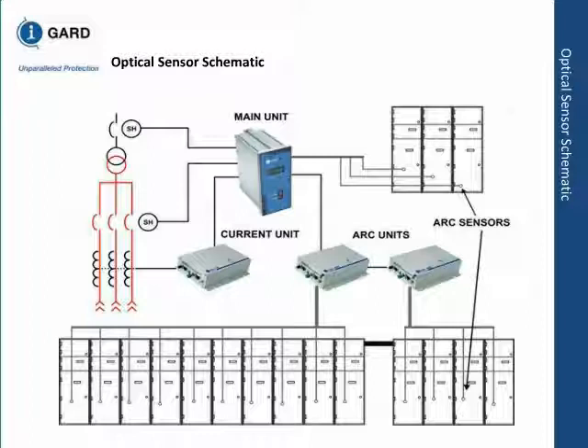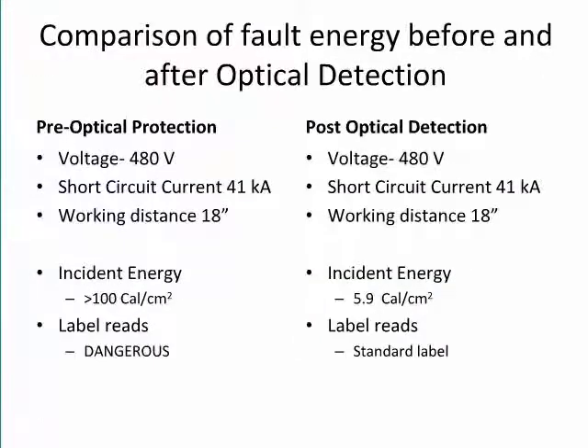Look at the same comparison. You have a 480 volt system. Short circuit current is about 41 kA, working distance 18 inches. Now this working distance is not from the front of the cubicle. This is from where the arc source is. So the arc source could be inside. Based on that, incident energy was calculated to be more than 100 calories per centimeter squared.